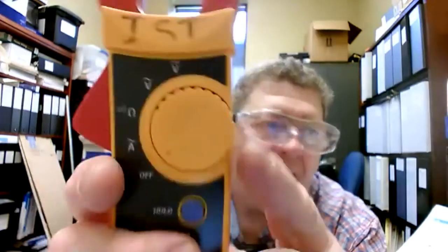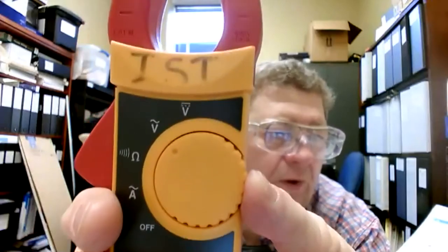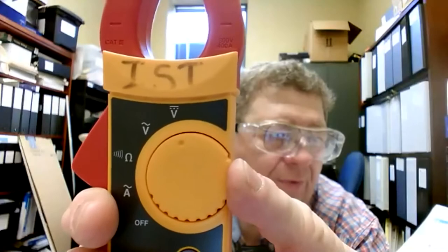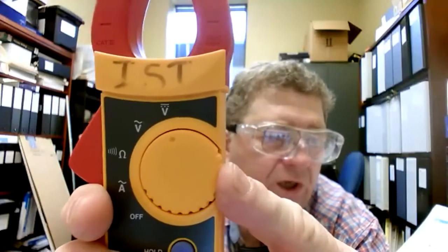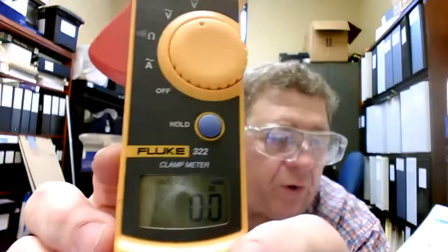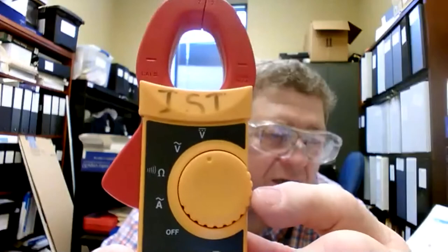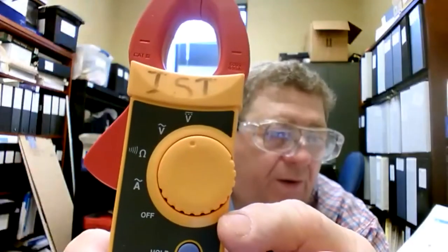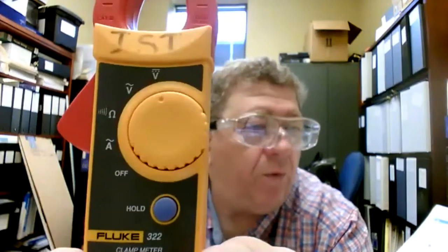Now, this one actually has two settings. It has an AC voltage setting with the wave on it, and then the DC voltage setting there. So you really have to think more using this meter. It tells you on the screen it says DC because you selected DC. If you're on the DC setting and you go to an AC circuit and check it, the meter's not going to tell you what you've done. It's not going to correct that display. You're simply not going to read the voltage. You may think it's dead if you check a 120 receptacle, but you've got the meter on DC volts. It's not going to read, and you may make a mistake and think the circuit's dead when it's not.